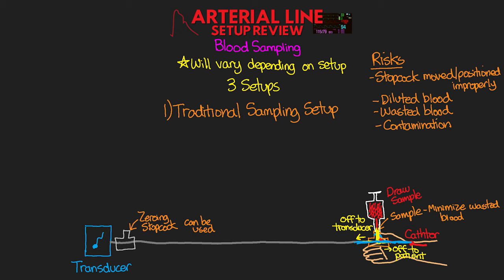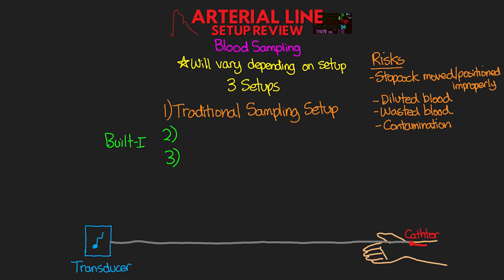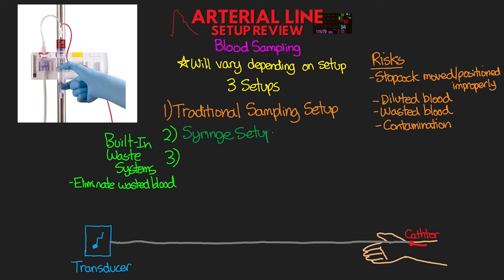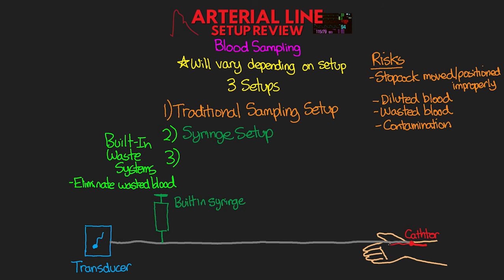Now, the other two potential ways to draw a sample are going to be with setups that have built-in waste systems. Now, these systems are better than the traditional as they eliminate the waste of blood. And there's really two main setups for this. The first setup is going to be the syringe setup. So this one has a built-in syringe near the transducer. When you're ready, you would turn your stopcock off to the transducer and then withdraw your waste into the built-in syringe. This setup still uses a three-way stopcock to attach and draw a sample, just like the traditional setup. Now, this still has some of the same concerns as the traditional setup, all except for the wasted blood. And this is because we have the waste in that syringe that's built into the system.